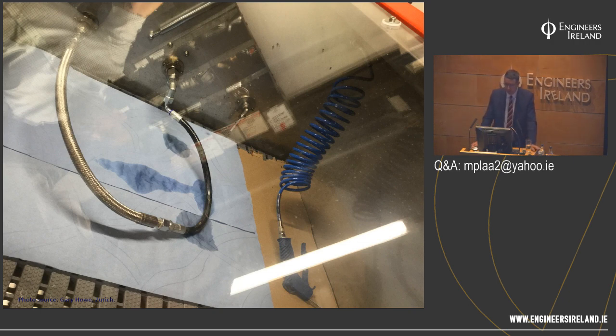Well, basically the issue was they weren't listed or tested for that intended application to work at 140 bar. The reason is they were rated to work at a high pressure, but they're pneumatic hoses. So if you can imagine a hose with another hose inside, on the outside you had hundreds of tiny pinprick holes. When it overpressurized, the idea was that the outer sheath discharged the overpressure through the holes in the outer sheath. So the air discharged out.